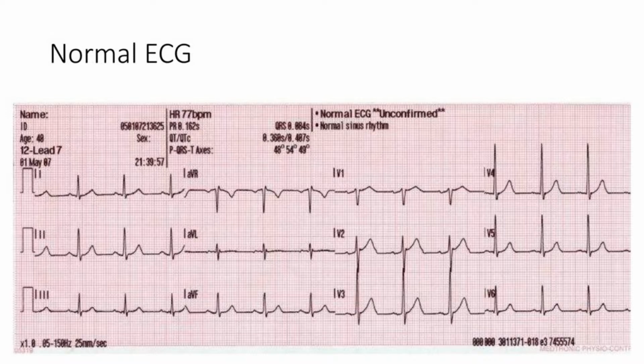You want to obtain a clean ECG by ensuring thorough skin preparation, eliminating any interfering electromagnetic waves or currents. If you are getting electrical artifacts, which can be common if you are running a generator, and you can print the ECG using the battery in it, that may filter them out and ensure you have a smooth ECG. So tampering with the filter settings of your ECG should be a last resort.